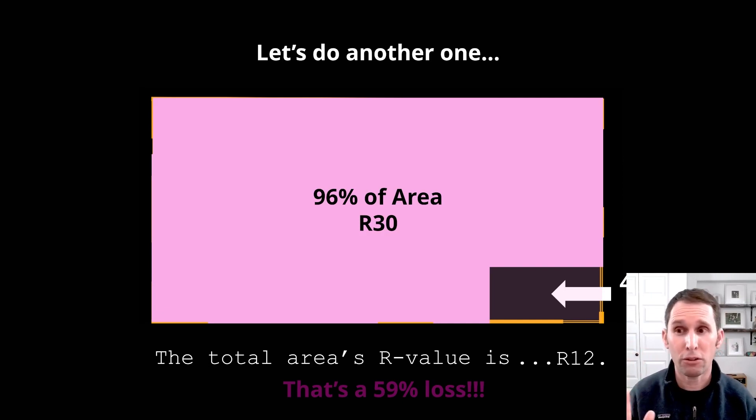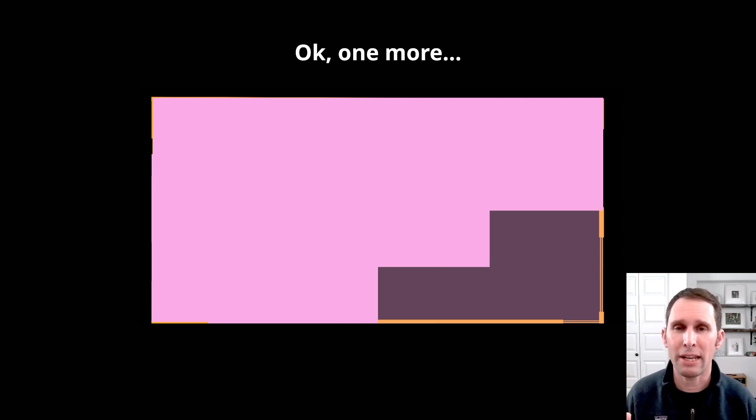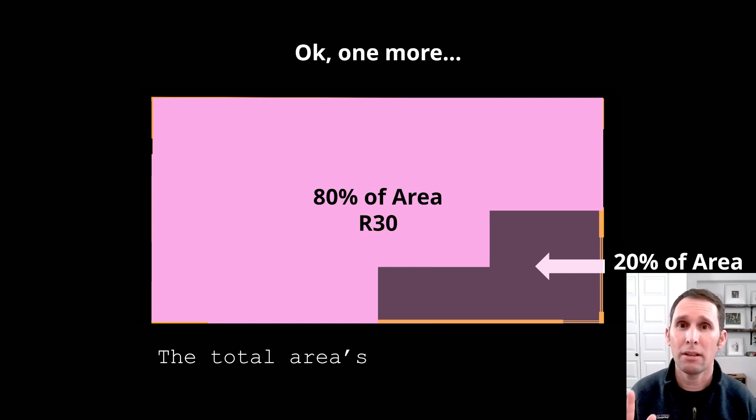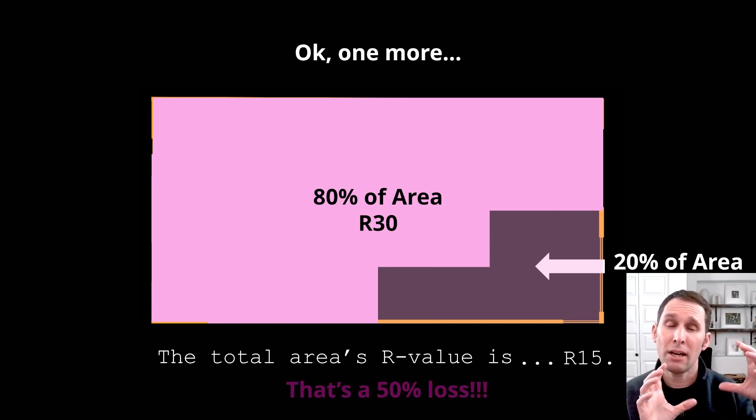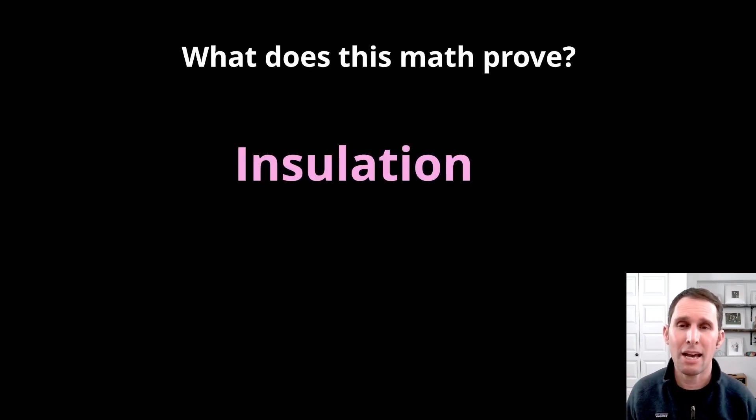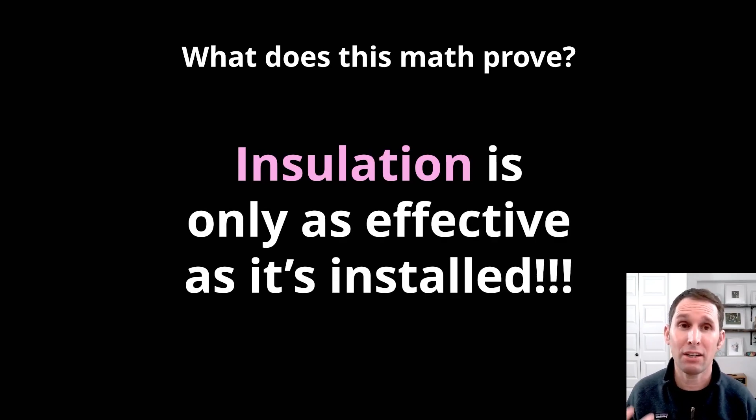Now, there's a really fancy formula where you use the inverses to come up with the additive of the different inverses. We're not going to go through that today, but just as an understanding of how important it is to make sure you have an effective and consistent insulation barrier. Let's look at one more example. Imagine you have an attic floor and 80% of the area is R30. 20% of the area is R5. There's a little bit of insulation. The total R-value of that area is actually R15. So, it's a 50% loss, even with only 20% having an R-value of R5. So, the sum of these examples and what this math really proves is that insulation is only as effective as it's installed. You have to have a consistent thermal barrier, a consistent amount of insulation for it to work well. So, when you start to ask the question, how much insulation do you need? It's really not just important to see how much you need. It's really important to see how well you need it to be installed.